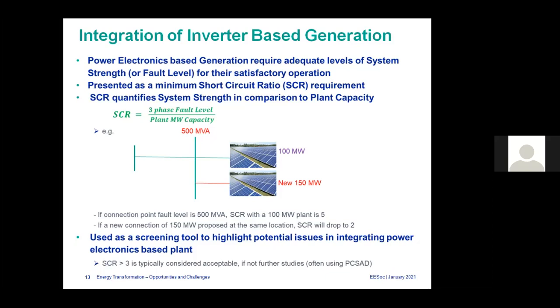Unless it's a very bad fault, which is not cleared for an extended period. But solar farms and wind farms might struggle sometimes. If the connecting location is very weak, we find that for some faults they can't ride through. They will trip by themselves. So inverter manufacturers normally specify an SCR level, typically around 2 at the moment. They say above 2, they are confident the inverters will be able to ride through a fault. But below 2, they suggest we do more studies.